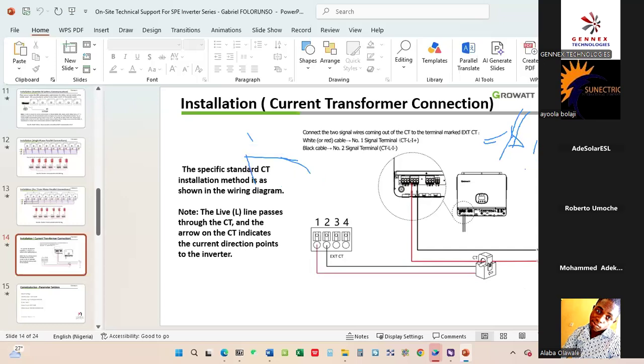You have to ensure the CT is installed, not inside the inverter. People ask this as if you're collecting your money - no, you should ensure your CT is installed close to the DB of the building. Mind you, this CT has a long wire already, so just extend it. Don't house it inside the mini flat of the inverter; it must come out and be close to the wall, the DB of the site. Please take note of that.